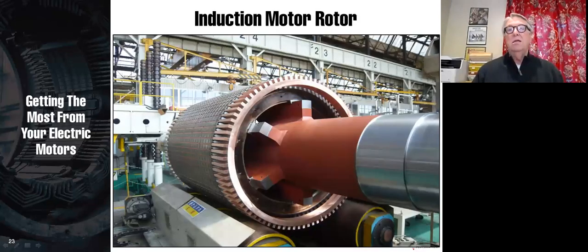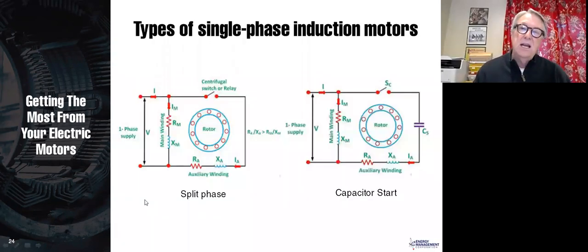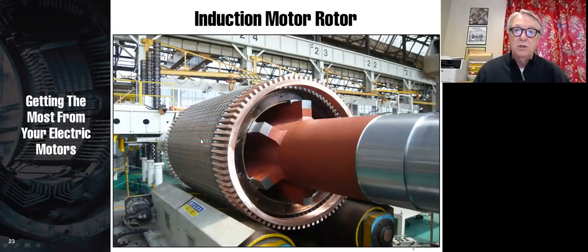Since you can't see them, I put in a slide of a much bigger motor. In this bigger motor, it's all done by hand, and it's easier to see how the rotor is constructed. So you can see we've got the iron to conduct the flux, and then here are your copper, in this case, could be copper or aluminum, your copper rotor bars, and the copper rotor bars are set in the iron, and then they are brazed to the copper end ring. So I love this picture because it's so easy to see the parts and pieces.